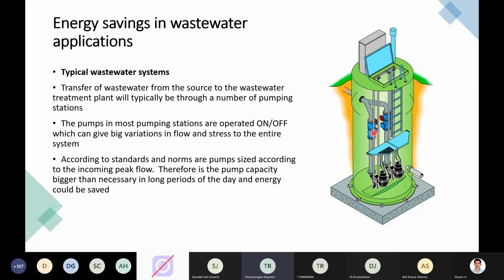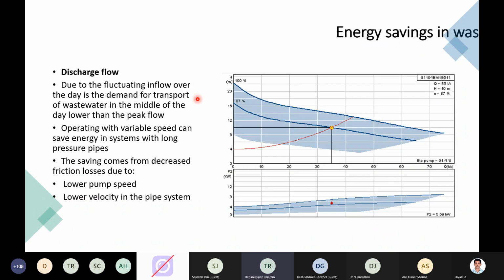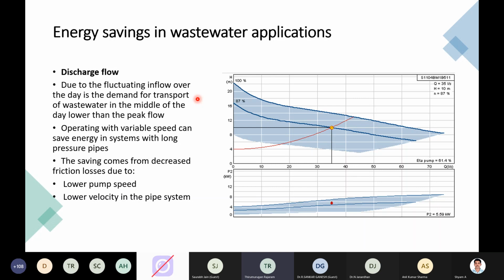So the challenge is on and off system operation, because this complete scenario is worked based upon your water level within the tank. When you have automation where you can find a float level in the tank, and when the float level reaches its setpoint, the pump will automatically start and stop. So even for submersible dewatering pumps in wastewater applications, adapting a VFD has more impact on energy savings, because you will not end up in higher head scenarios. You can precisely operate at your required duty point.